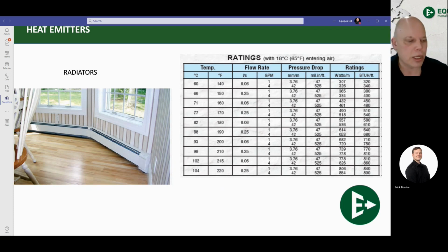Kind of drives me a little nuts because it's about as close to 0 as you can get without being 0. Essentially, what you need to know is that for baseboard radiators, it's going to be essentially just the copper tube size that's going through this. So you can use your 3/4 inch or 5/8 inch piping head loss chart to figure out your head loss through these guys here as well. Because again, these milli-inches per foot do not translate well into PSI or into feet of head.